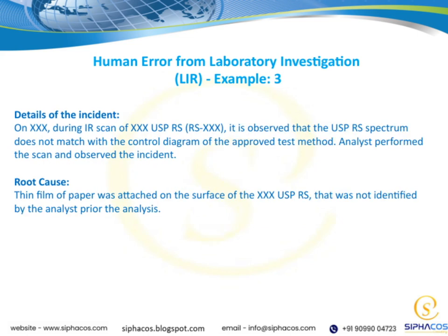On this slide, I will walk you through the details of the incident that occurred during the IR scan of the XXX USP RS, specifically RSXXX. So, on a certain date, during the scanning process, we noticed that the spectrum obtained did not match the expected control diagram outlined in our approved test method. The analyst performed the scan and observed this discrepancy firsthand, which prompted further investigation.